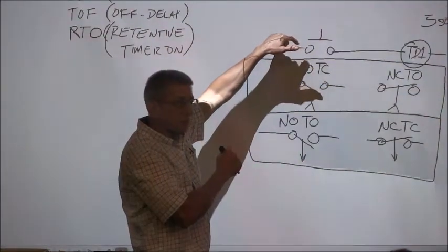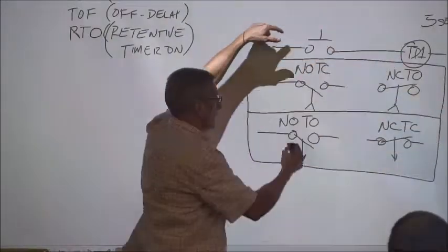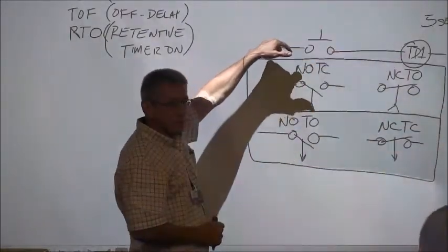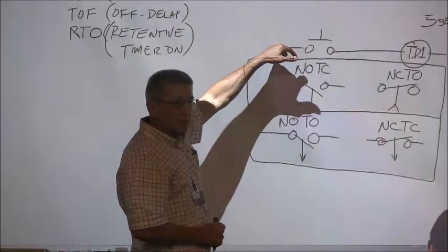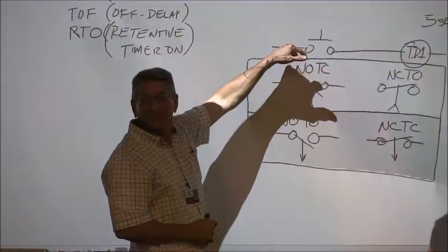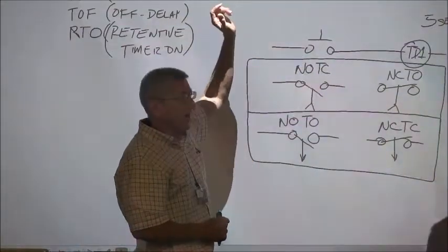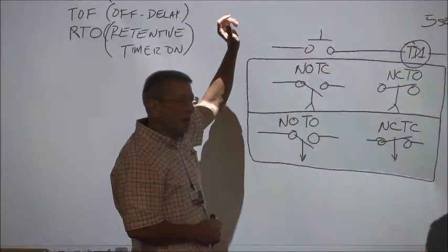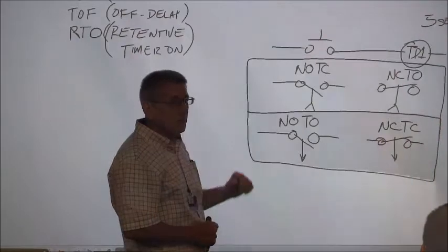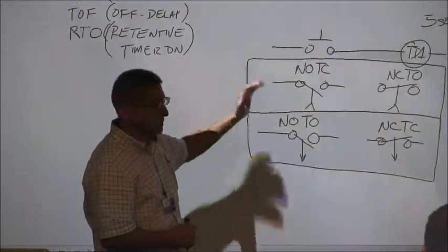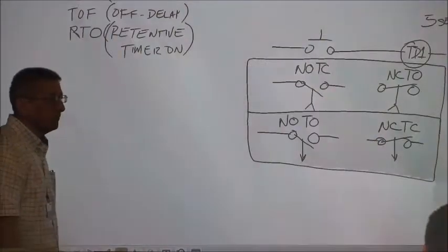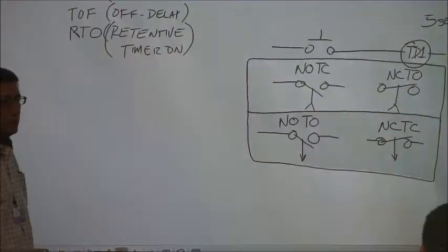As soon as we press the button, as soon as that relay gets energized, it closes instantly. Then when does it start timing? When you take your finger off the button. That's right. As soon as we de-energize that timer, that's when it starts timing. It times for 5 seconds after it's de-energized, and then it opens up. Good?